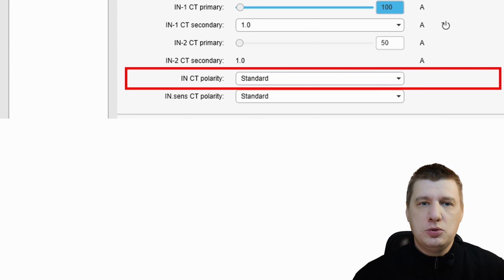Polarity determines how the relay compares the angle of the residual current against the residual voltage. This is vital for directional earth fault protection. If your polarity is inverted, the relay might see a forward fault on your line as a reverse fault behind it, meaning it won't trip when it should.